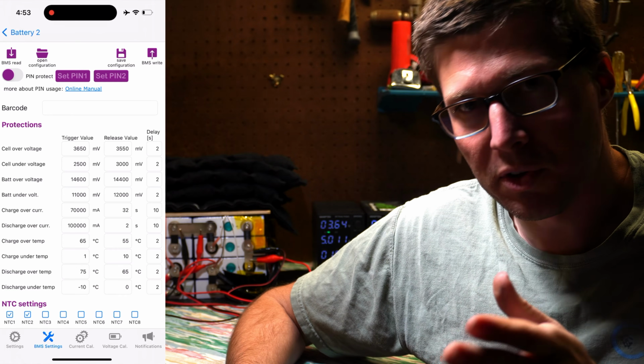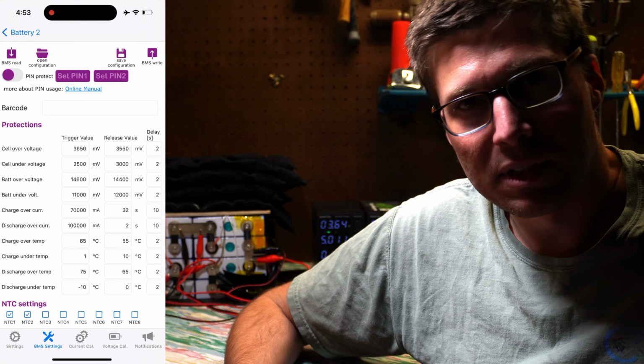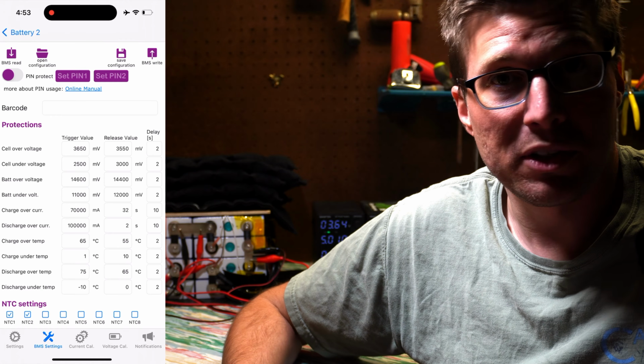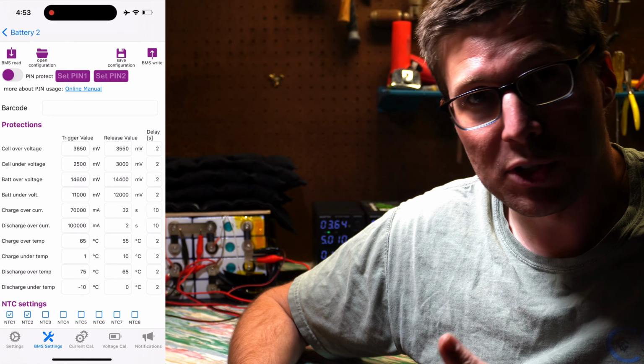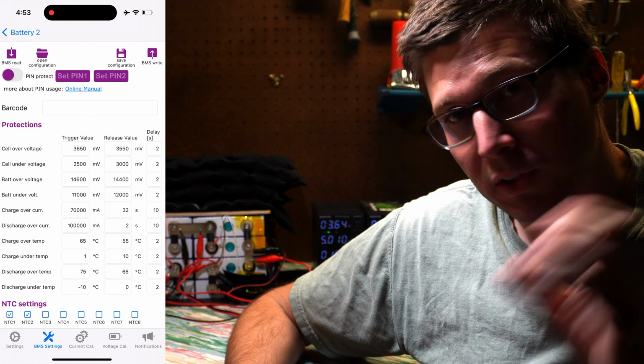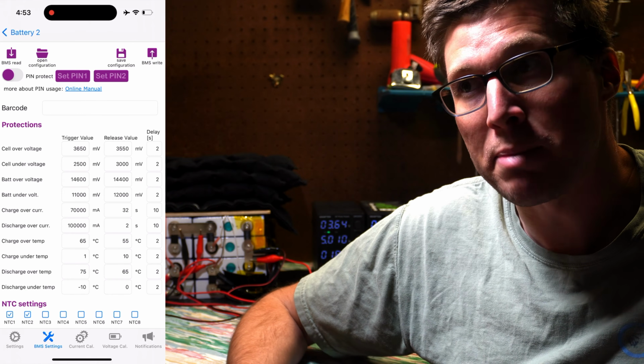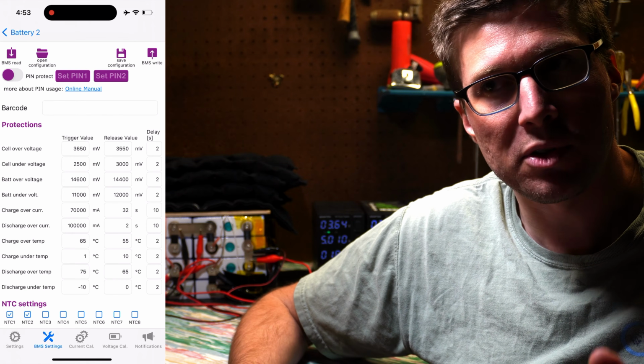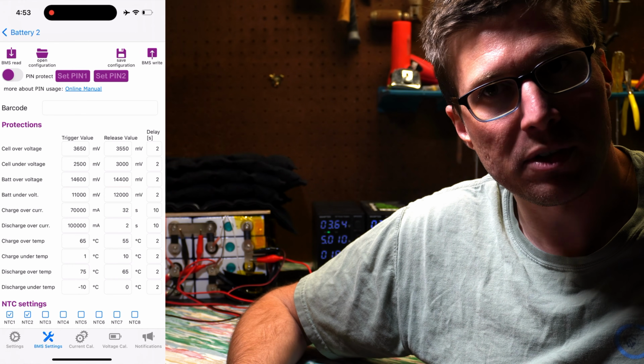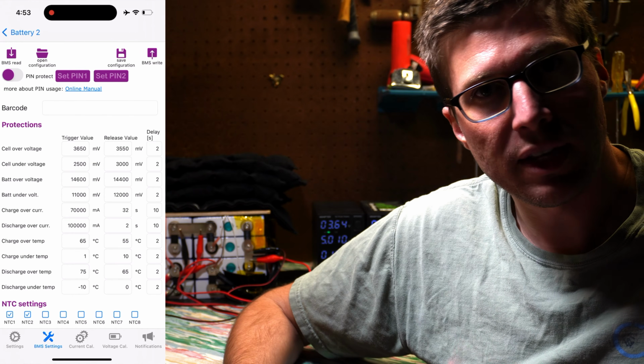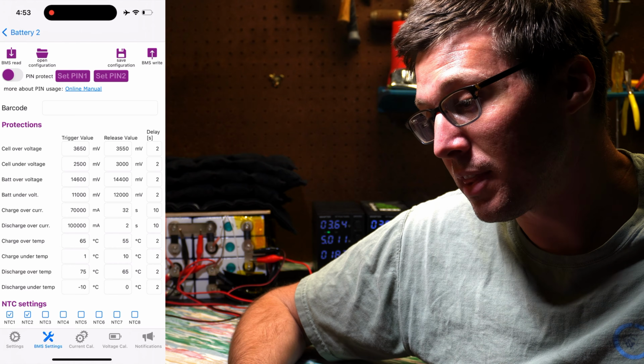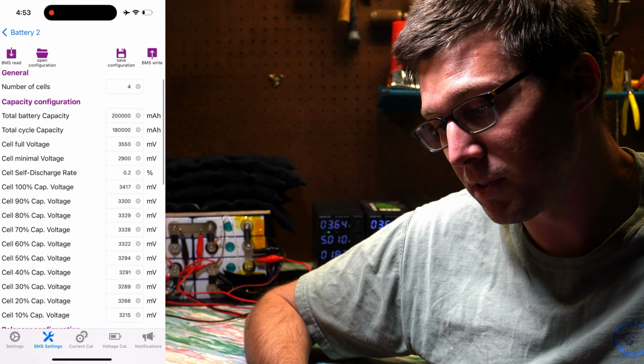If you set it longer than that, you could hit something because you have no motor until it comes back on. For house loads it's not as big an issue - your lights just turn off and come right back on. It's a nice warning telling you you're using too much, so turn stuff off and take it easy. That's how we set the BMS on this.